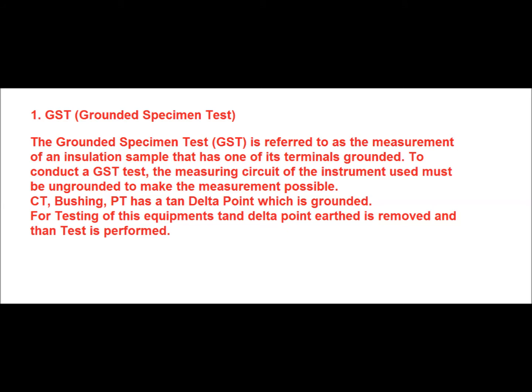In the case of CT bushing and PT that has a tan delta point which is normally at ground or earth, to test this equipment in a substation, the tan delta point is removed from the earth. Then one electrode is connected to the HV side and the other is connected to the tan delta point, and then the test is performed.